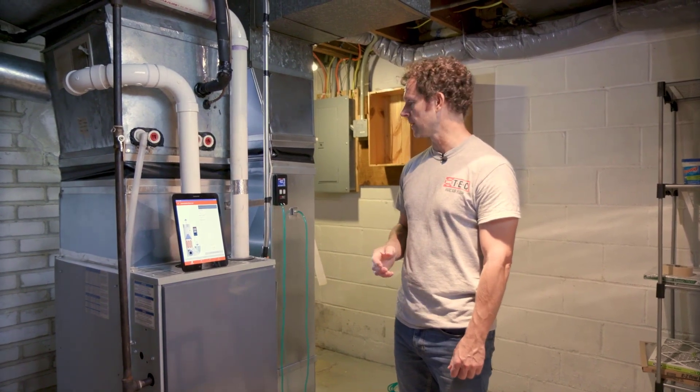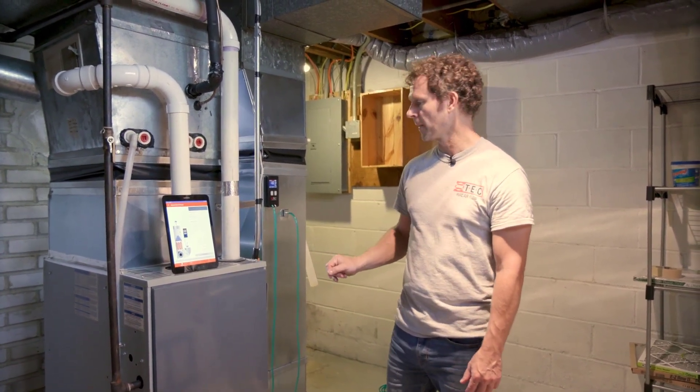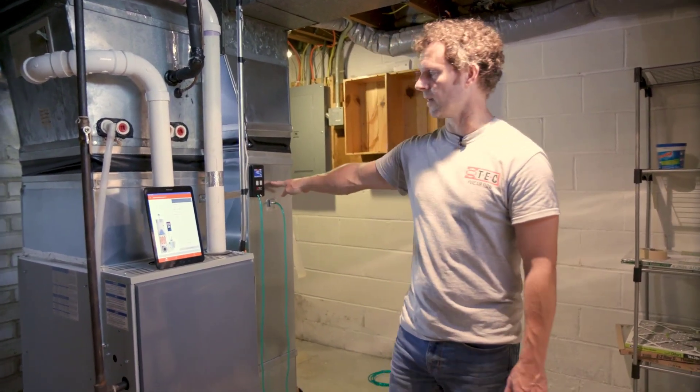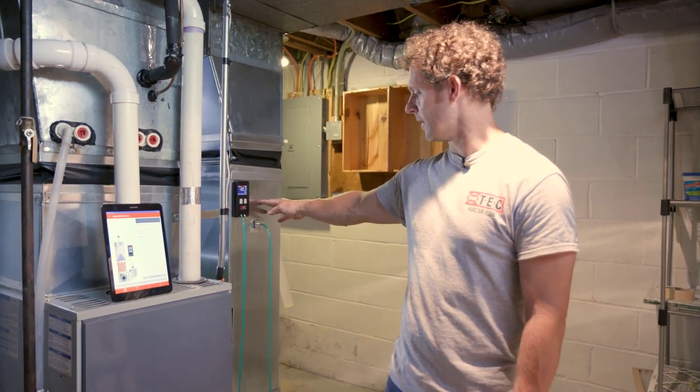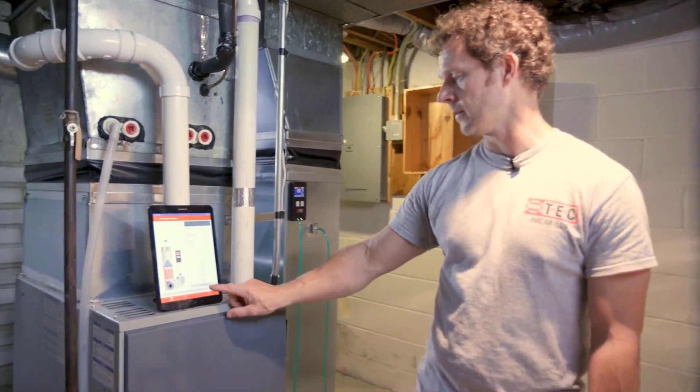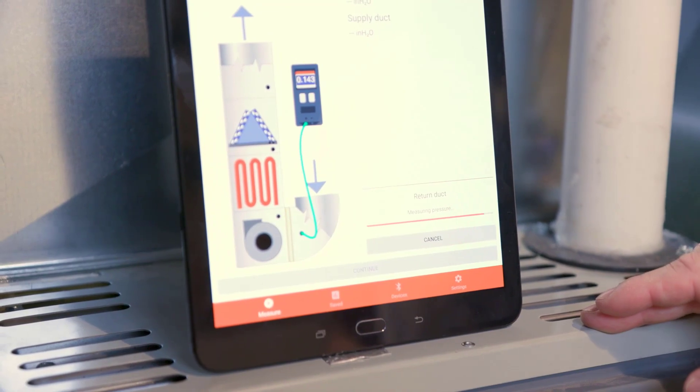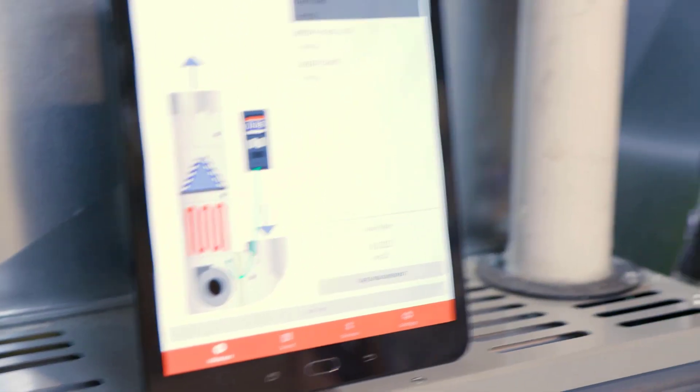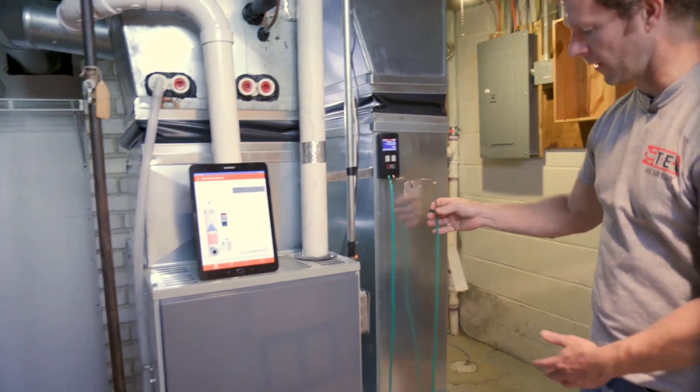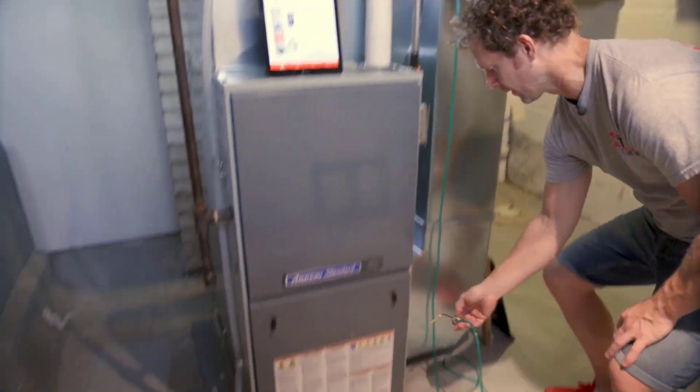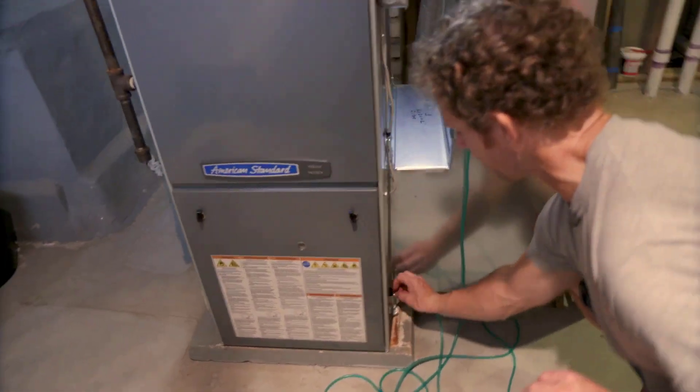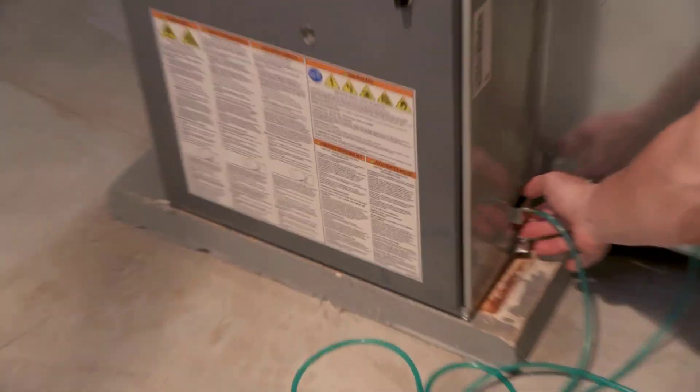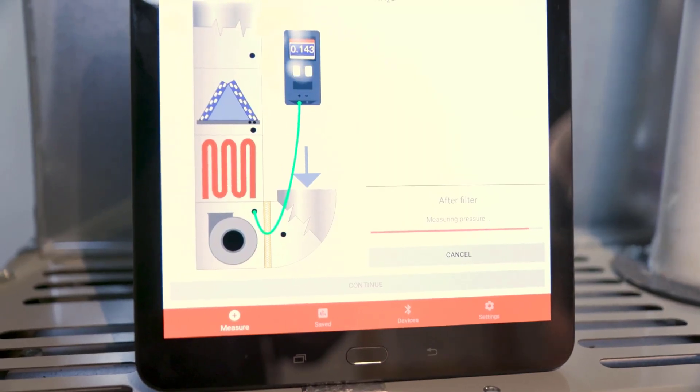We're going to be using the digital TrueFlow to do that, and I've got everything set up here. We're going to start by taking a static pressure measurement on the return side. That's going to then prompt us to move the location, so we're going to move now from the return side of the filter to the furnace side of the filter right here, and again we'll take our measurement.